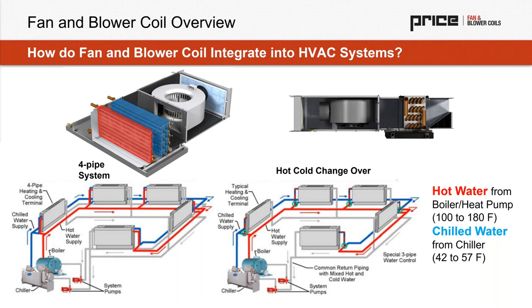When we look at a reheat configuration, some markets would use both coils at the same time to dehumidify and temper air, so we can treat a latent load without doing too much sensible cooling. We do see that more and more in states with really less constraints on energy code. It happens more as you move southeast through the country, but isn't something that is really a feasible application for Massachusetts.